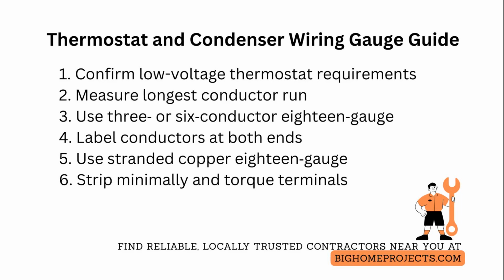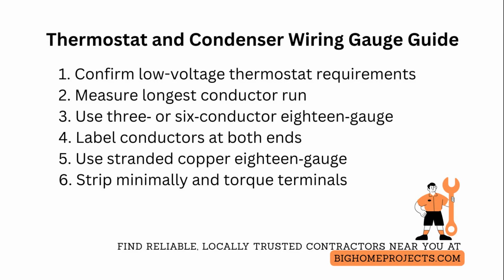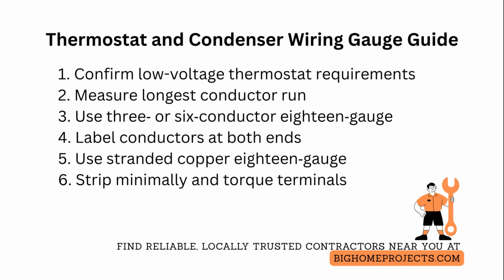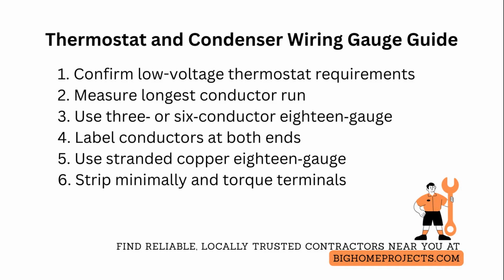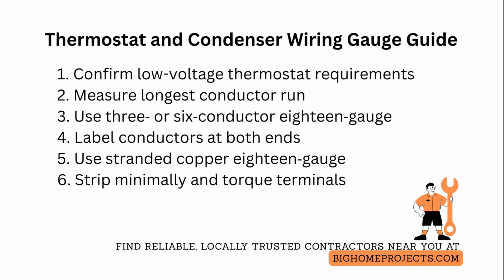If using thermostat wire in walls, choose cable rated for in-wall installation and keep it separated from high-voltage wiring by at least the distance required in your local code. When terminating, strip only the minimum insulation. Tin the ends only when the terminal design allows it, and tighten screws to the torque the equipment manufacturer specifies to prevent high-resistance joints that cause intermittent operation.